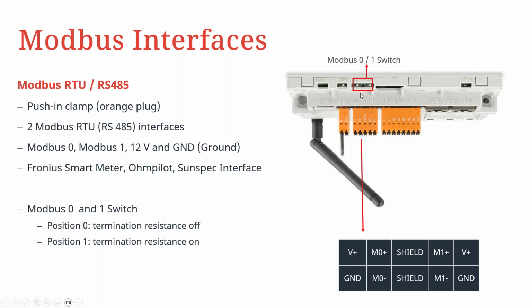So for example, if we're communicating with a smart meter, we should enable the 120 ohms terminal resistor on the pilot here, and then also on the smart meter in this instance. And I must mention here that, although not fully covered, modern or new smart meters that are being manufactured by Fronius now come with integrated 120 ohms terminal resistances that would have to be actuated simply by looping one end to another with jumper cables. So we don't have to use a physical 120 ohms resistor to do so. Good. So having said so, turning it off basically turns off the terminal resistor. So in this position, there will be no communication.